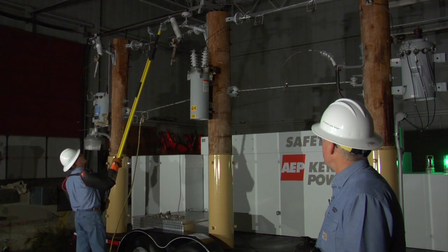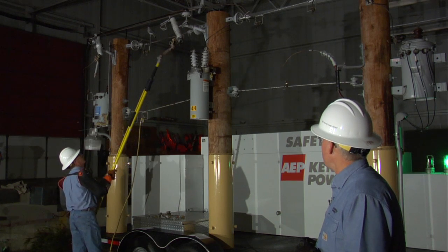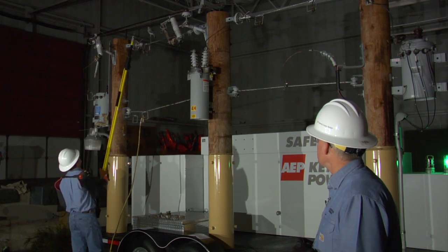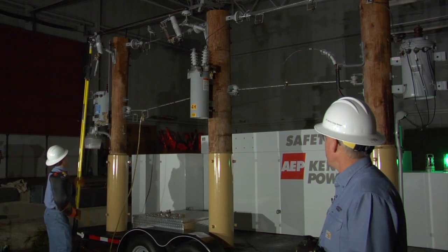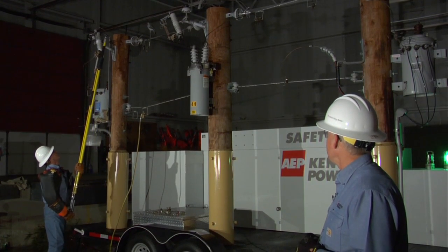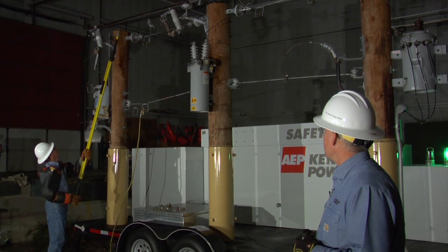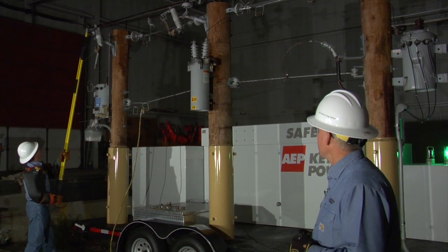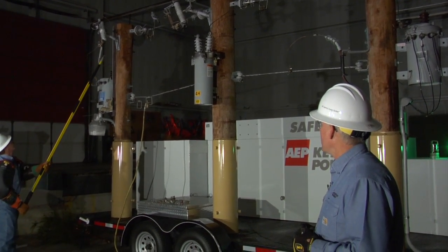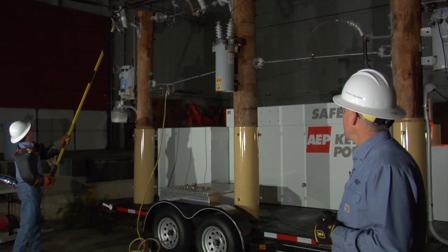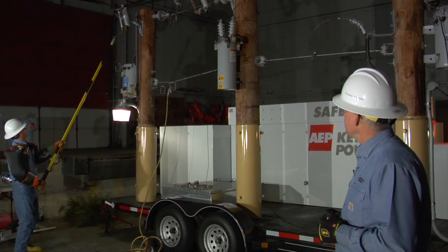Above the recloser, we have a bypass cutout. It allows us to bypass the recloser, taking it out of service for maintenance and for other purposes. The power will flow over to the last pole into the transformer cutout, which holds a fuse for the protection of the transformer underneath it.